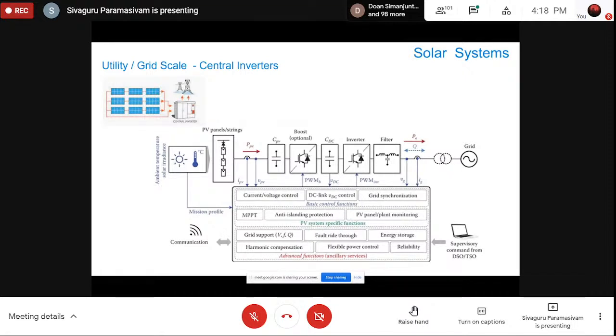What it does is basically the DC, which is coming from the PV, it switches and then converts to the AC voltage. And when we have the switching, you can see here in this case an L, C, and L filter. There is an inductance, and then there is another inductance in series, and in parallel there is one capacitance. The reason for having this kind of LCL filter is that for this kind of system there is a huge amount of harmonics, and just an L filter or a C filter will not work, so we have to have this combination.